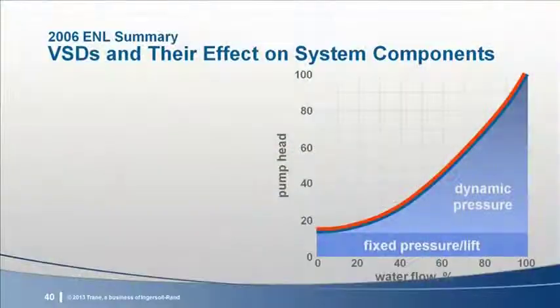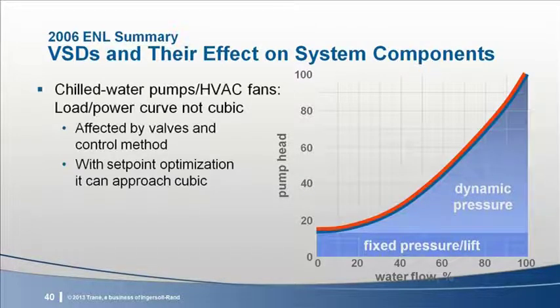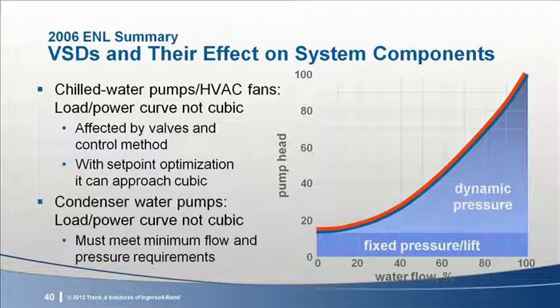Chilled and condenser water pumping systems both have a fixed or controlled pressure component and have a minimum flow requirement. These prevent the pump energy from following our ideal curve. Specifically, in many variable flow chilled water systems, there is a system differential pressure set point the pumps must meet. Depending on the pump control logic, that may be fixed or somewhat variable. Also, there is a minimum allowed chiller flow which prevents the system flow from following the system load curve to zero. For condenser water systems, the lift from the tower sump to the distribution nozzles is a fixed value, and cooling towers too have minimum flow requirements. The chart shown here provides an indication of how these fixed pressures and minimum flow requirements prevent the pump's power draw from following the ideal curve.